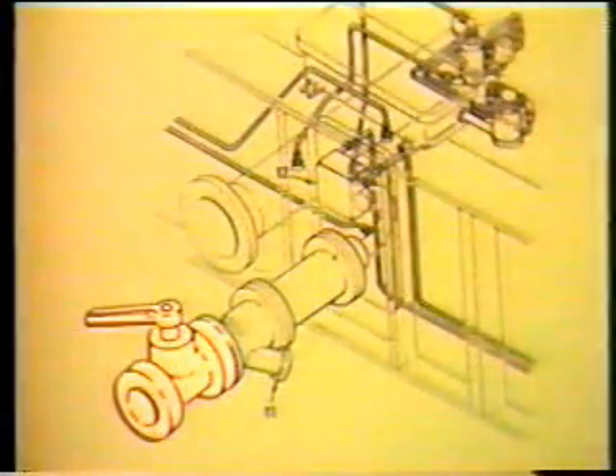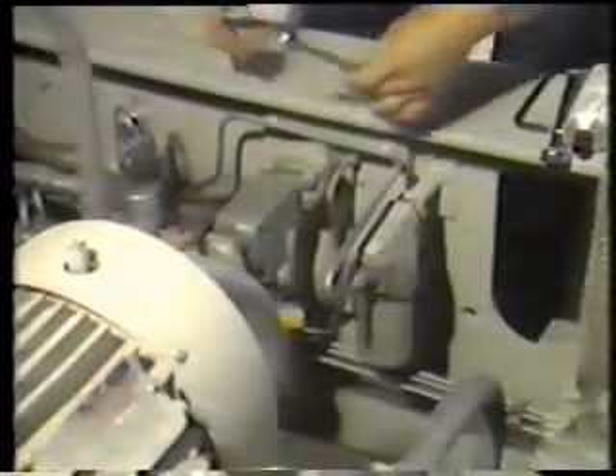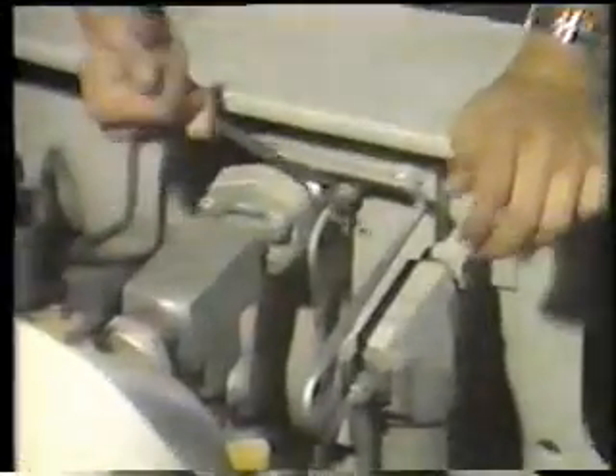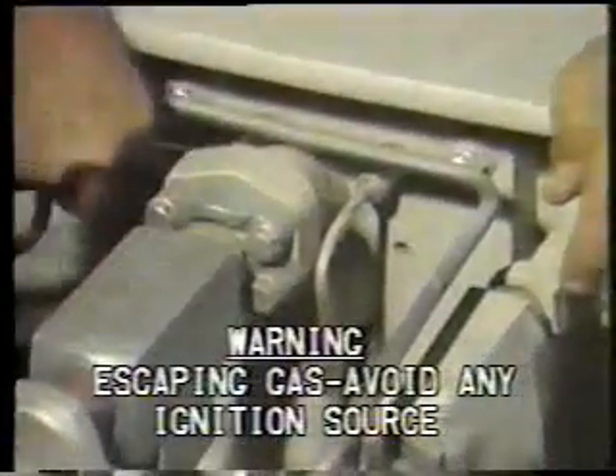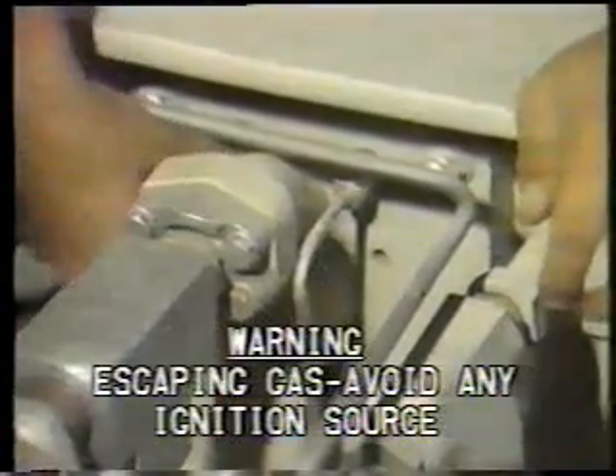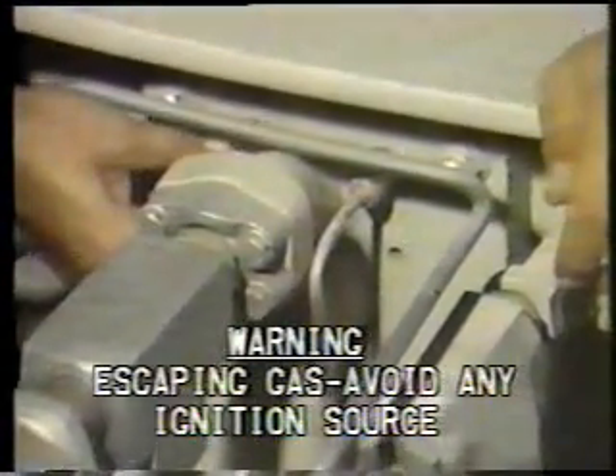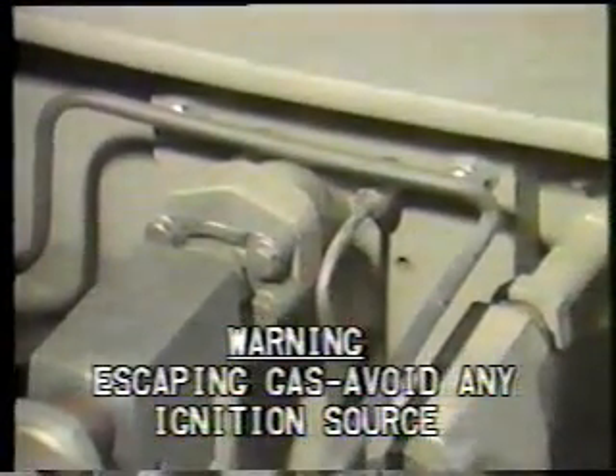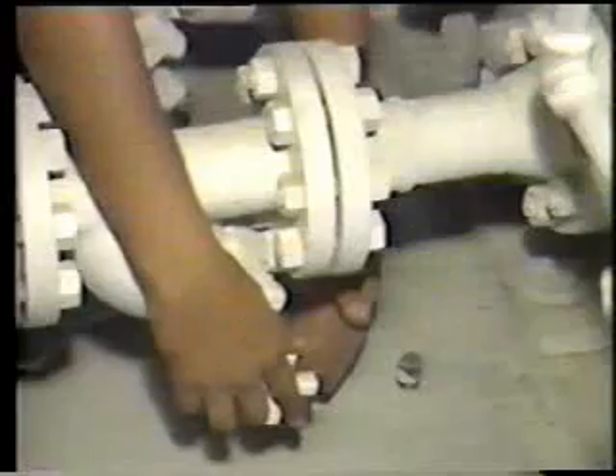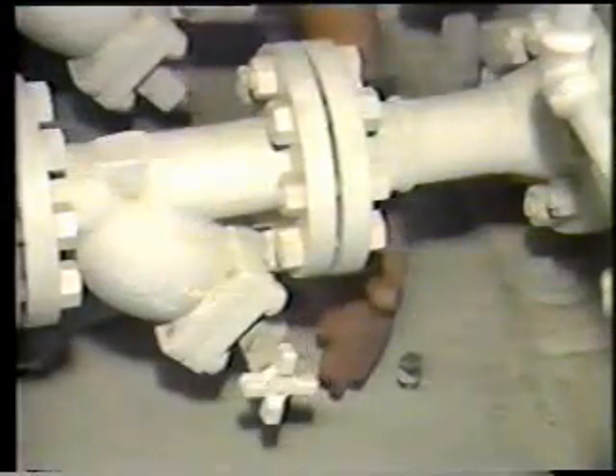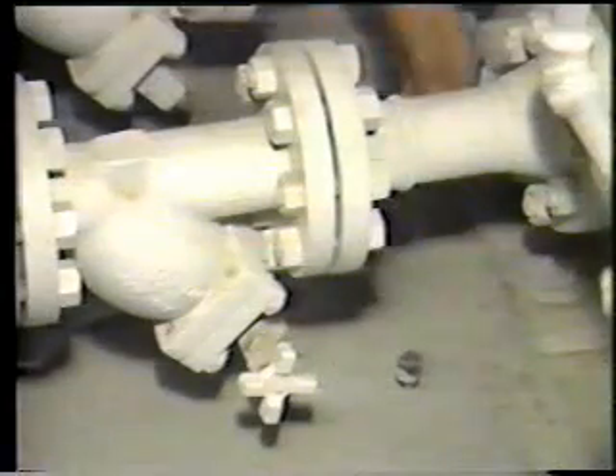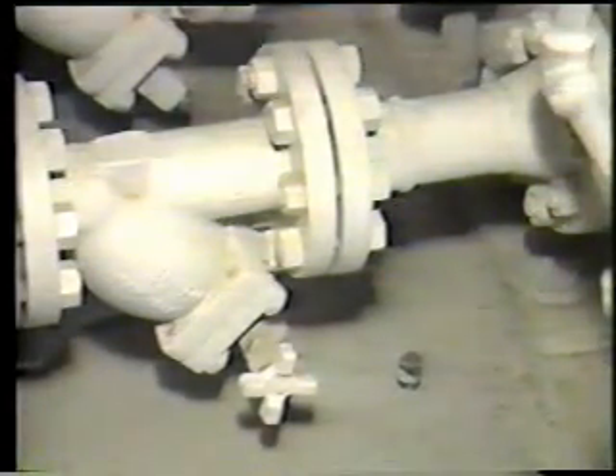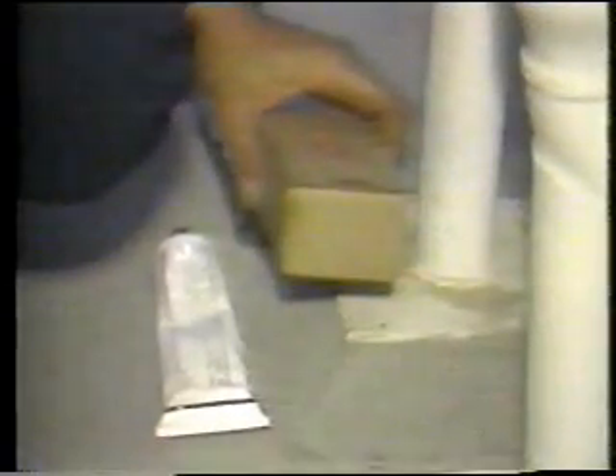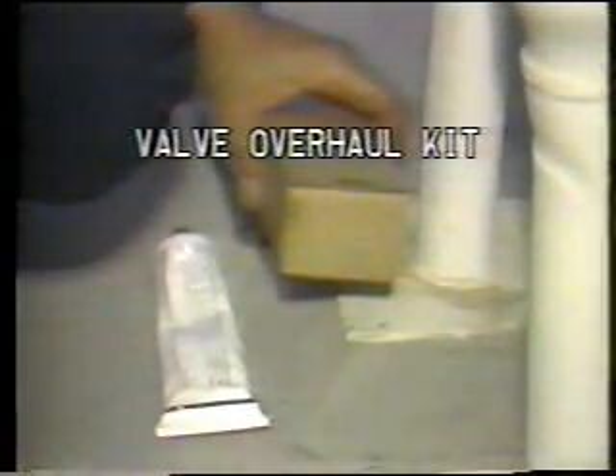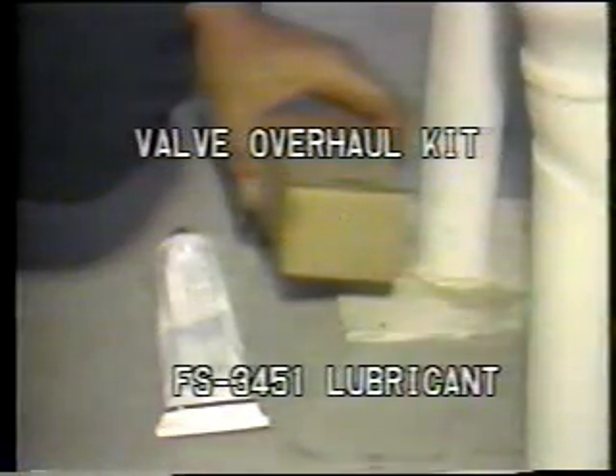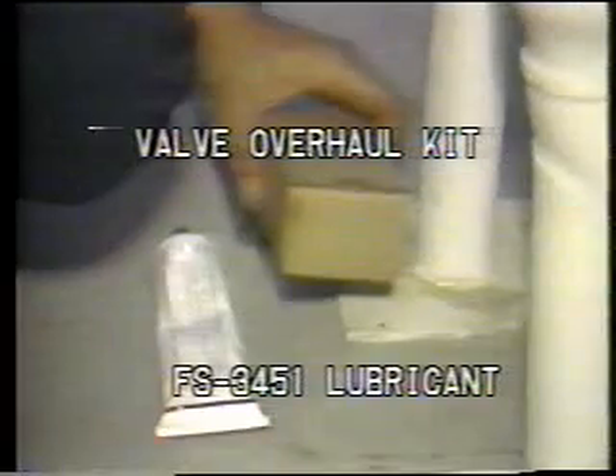If no valve exists for the bleeding of this gas to the vent, pressure may have to be allowed to escape from a pressure fitting. Warning: the escape of gas into the atmosphere can be a serious hazard. Use extreme caution to avoid any source of ignition and ensure that the area is well vented. Before the system is pressurized, a quick-acting 1/4 turn valve and plug should be installed in the gas strainer cap. Materials required for this job are one Versa valve overhaul kit for each valve, and Dow Corning FS 3451 fluorosilicone lubricant.